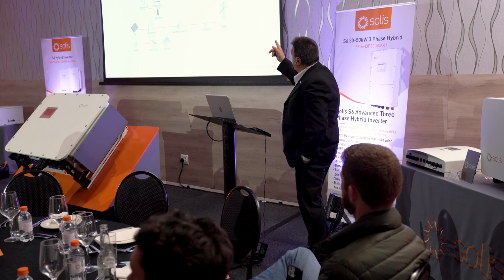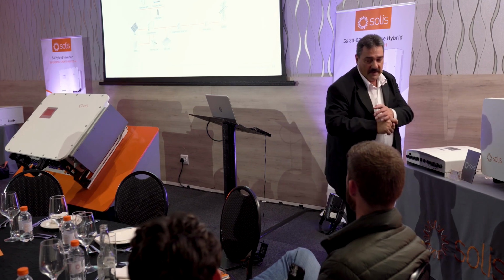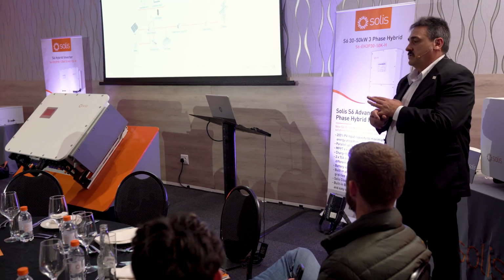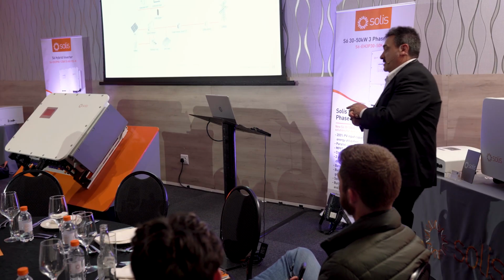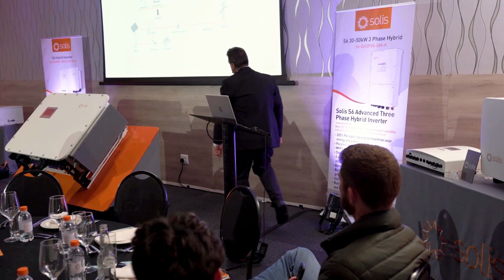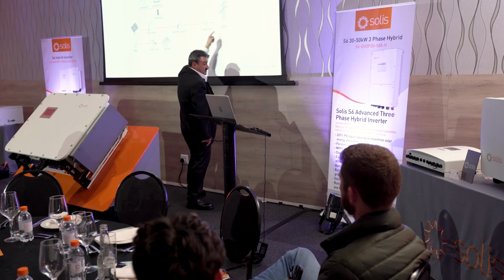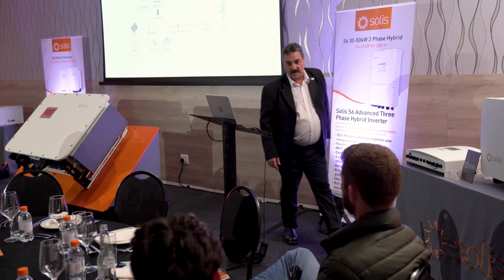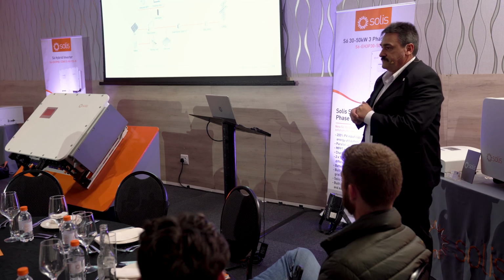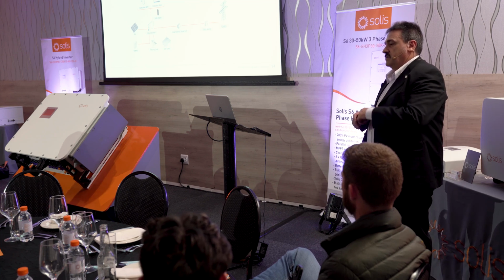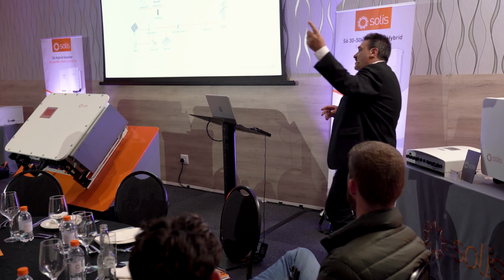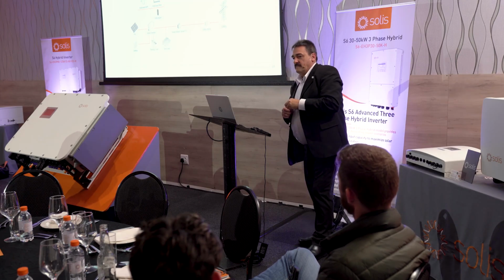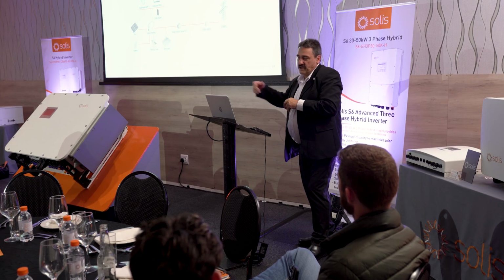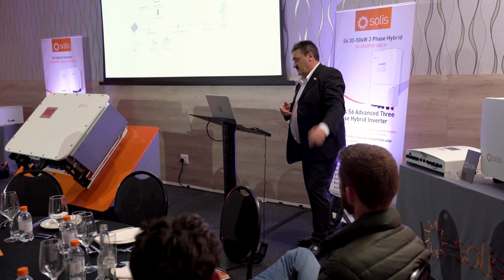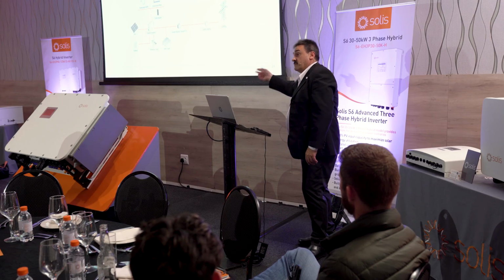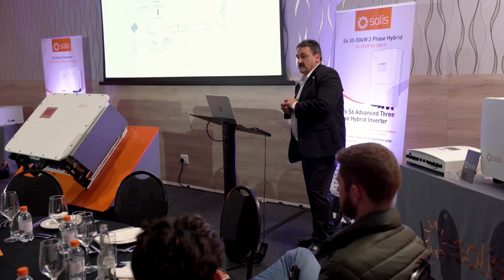So in excess electricity sold first, the backup load port is still priority number 1. But the second priority now changes to power coming this way, and the battery becomes the third priority. In other words, you're not going to use as much battery, but you want to sell the PV power back to the grid. And if you're lucky enough to have a big battery bank, and it's charged full, tonight you can discharge that power, and it will send it back to the grid. Okay, so energy arbitraging.